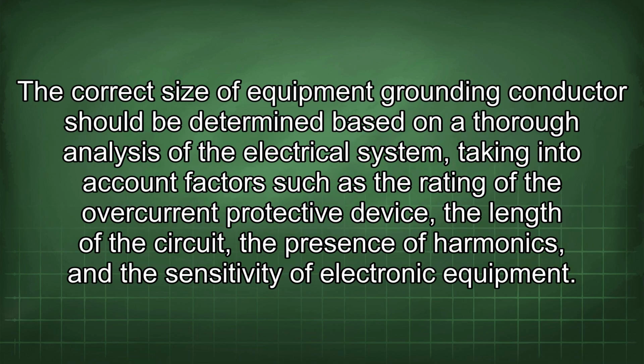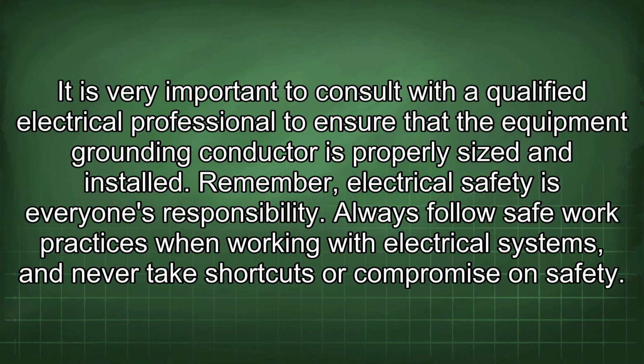The correct size of equipment grounding conductor should be determined based on a thorough analysis of the electrical system, taking into account factors such as the rating of the overcurrent protective device, the length of the circuit, the presence of harmonics, and the sensitivity of electronic equipment. It is very important to consult with a qualified electrical professional to ensure that the equipment grounding conductor is properly sized and installed. Remember, electrical safety is everyone's responsibility.